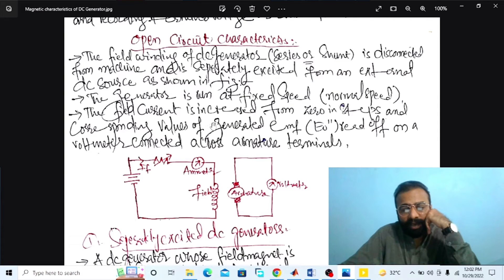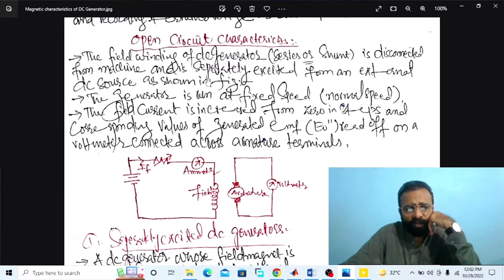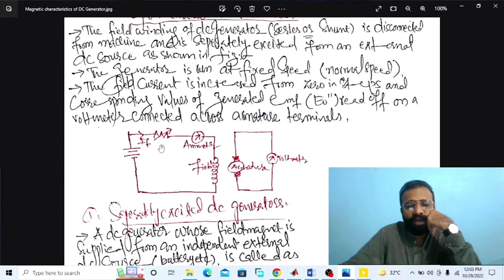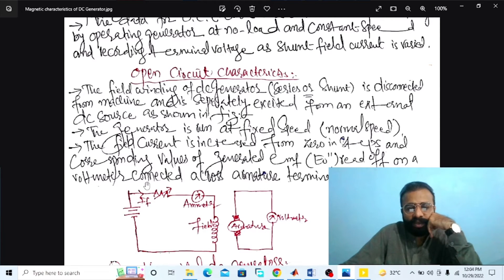The properties of the open circuit characteristics: the field winding of a DC generator is disconnected from the machine and separately excited from an external DC source. The generator is run at fixed normal speed. The field current is increased from zero in steps, and corresponding values of generated EMF E0 are measured by a voltmeter connected in parallel across the armature terminals. The main objective is to vary the field current and record the terminal no load voltage E0.